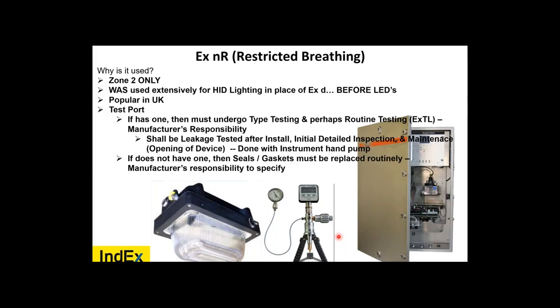If it does not have a test port, well, then the seals and gaskets must be replaced routinely, and it becomes the manufacturer's responsibility to specify that. Now, let me tell you, if you've ever dealt with lighting that doesn't have a test port, you have to change the seals every single year, according to some manufacturers.